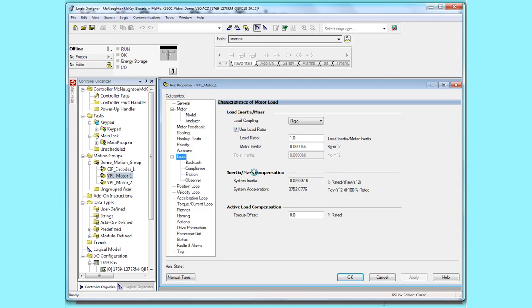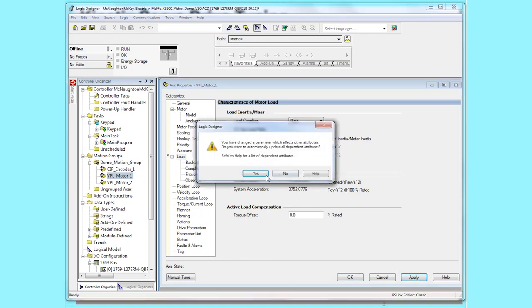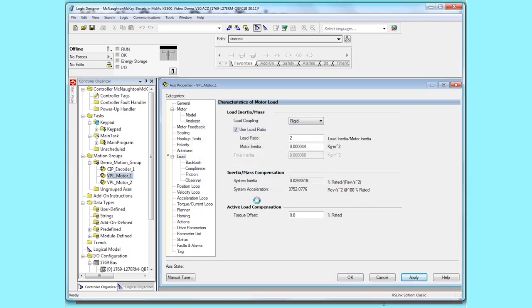Now practice with your axis and see how the axis responds. If you don't get the response you want, incrementally increase this number to two, maybe even to as high as 10. Typically a range of four to seven is a good number. Note that too high of a number can create instability in the axis.